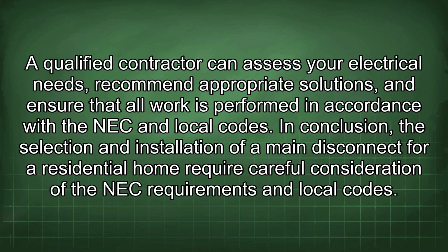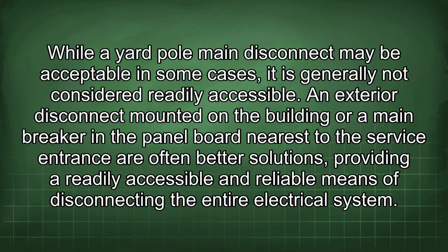A qualified contractor can assess your electrical needs, recommend appropriate solutions, and ensure that all work is performed in accordance with the NEC and local codes. In conclusion, the selection and installation of a main disconnect for a residential home require careful consideration of the NEC requirements and local codes. While a yard pole main disconnect may be acceptable in some cases, it is generally not considered readily accessible. An exterior disconnect mounted on the building or a main breaker in the panel board nearest to the service entrance are often better solutions, providing a readily accessible and reliable means of disconnecting the entire electrical system.